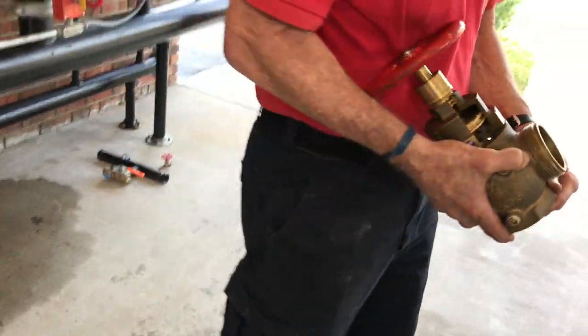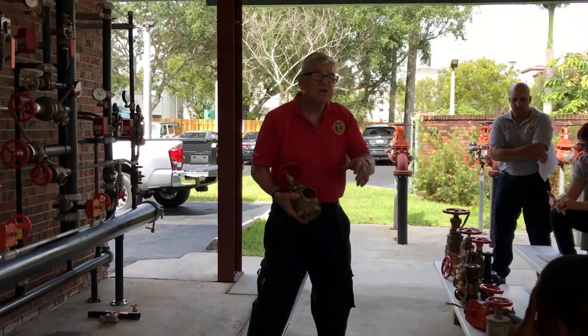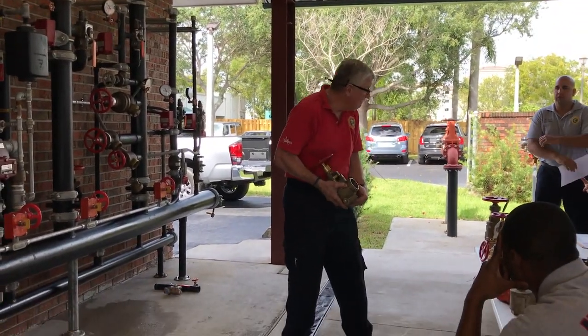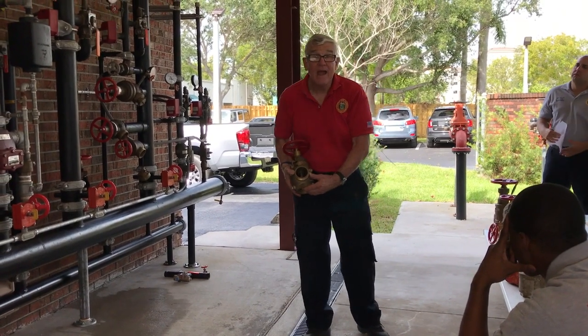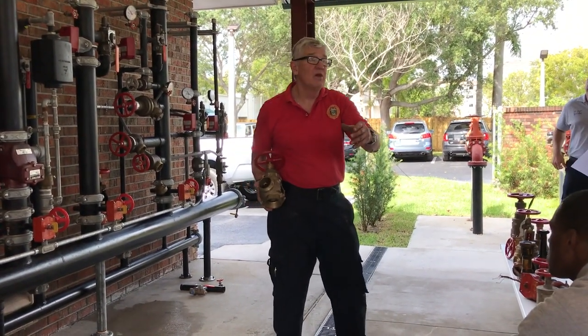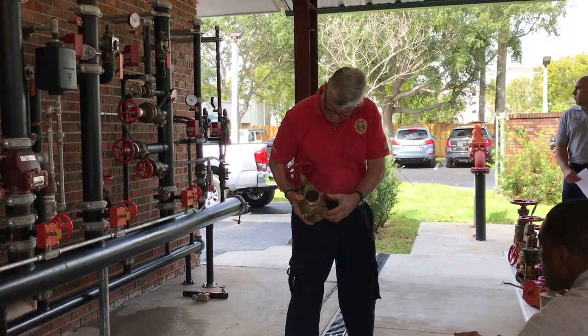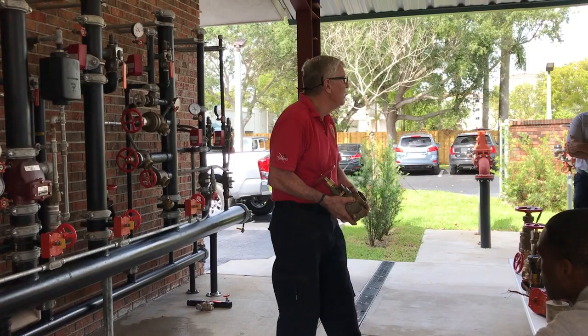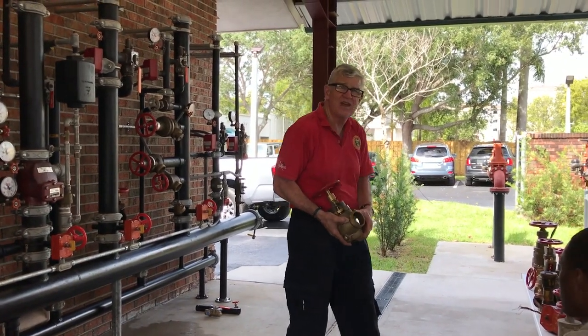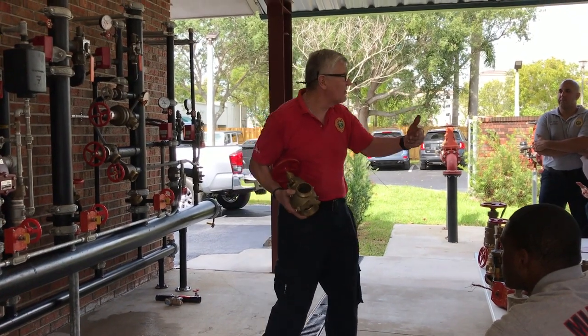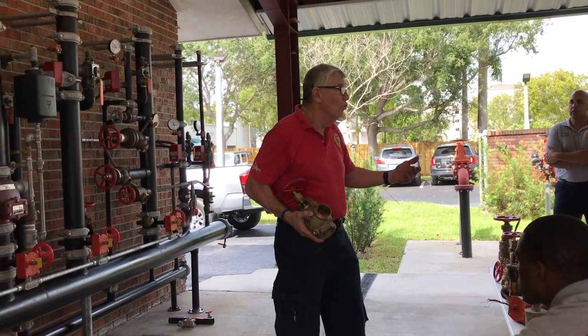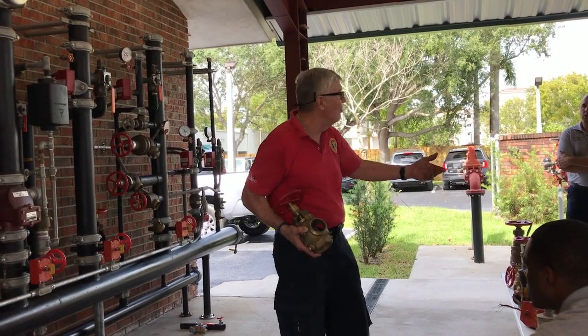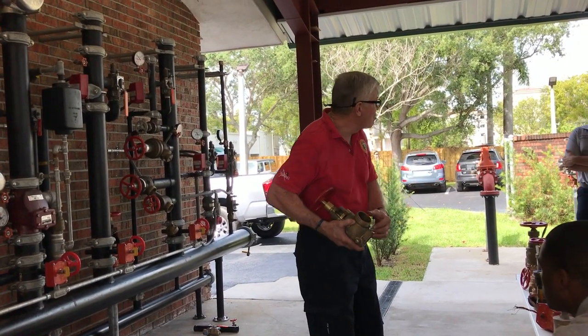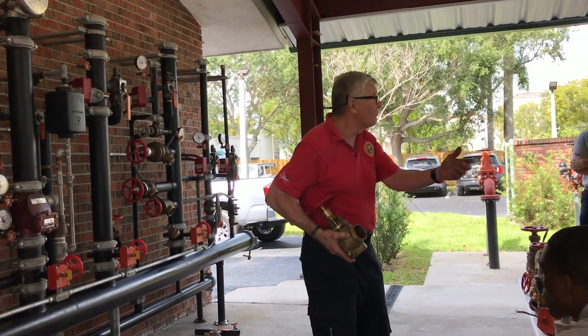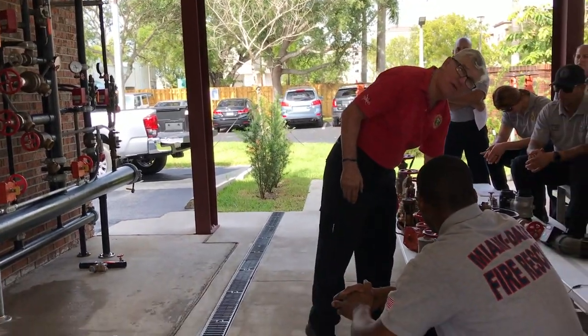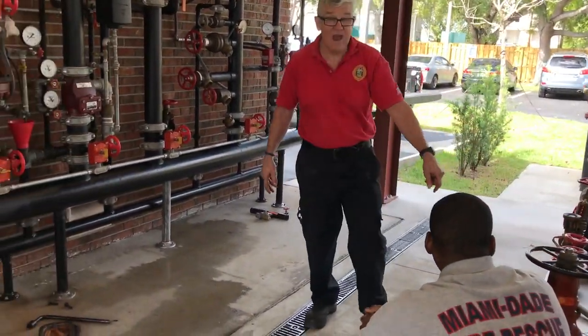What is required is every year, this outlet valve has to be tested with a pressure cap gauge to at least bump it off of its seat, and to make sure that the pressure is between 100 and 175 in static. Can you imagine, you just let this valve sit for 5, 10, 15, 20, God knows how many years without exercising it or flowing? Would we tolerate that with a piece of fire apparatus? No. Tank to pump valve, internal components immersed in water. Didn't flow for 10, 15, God knows how many years, how reliable would that valve be? We're staking our life on this.